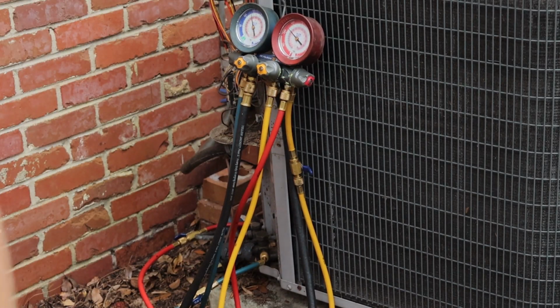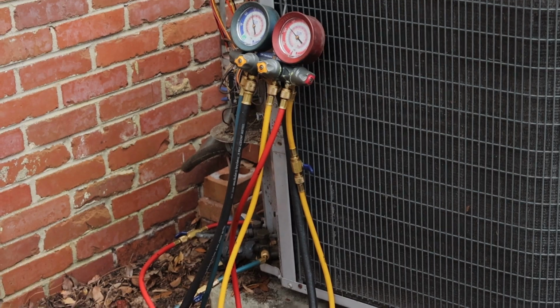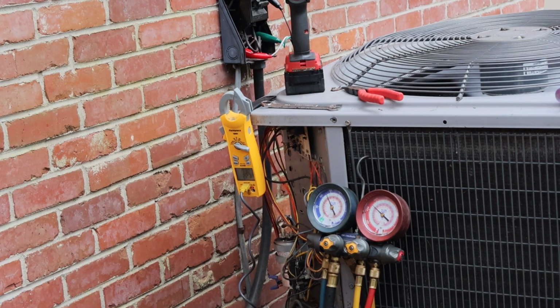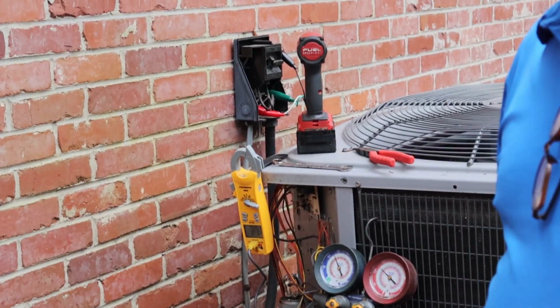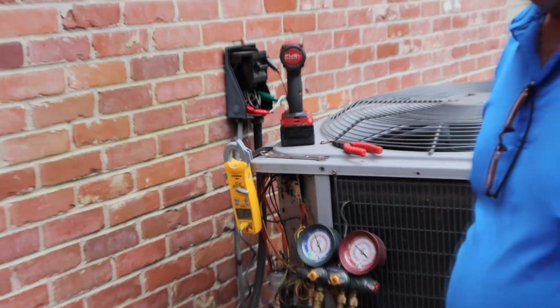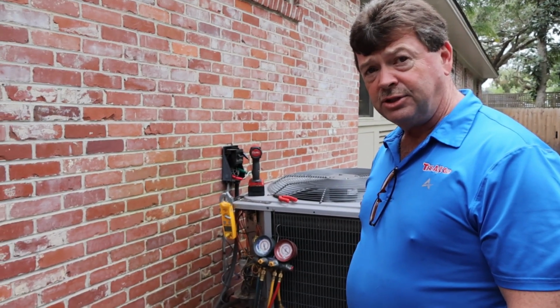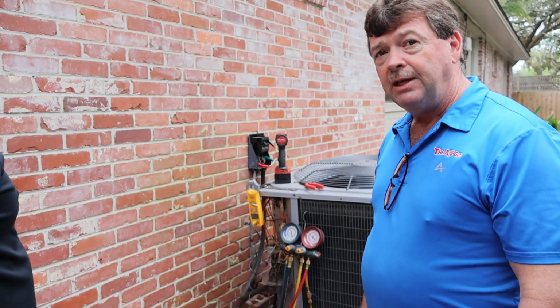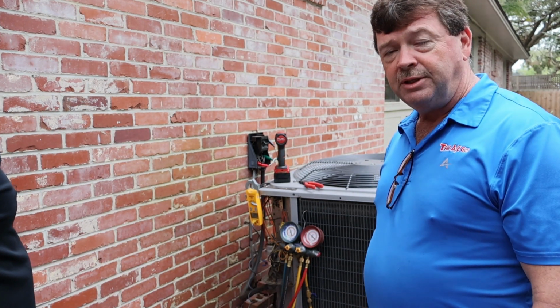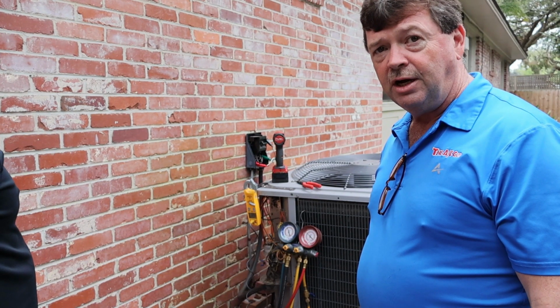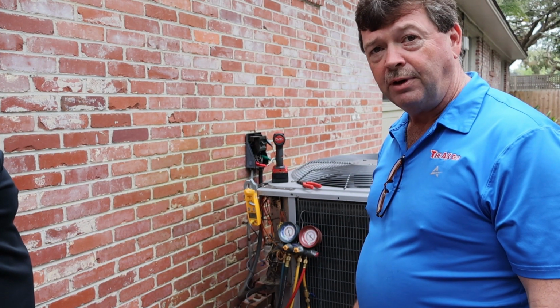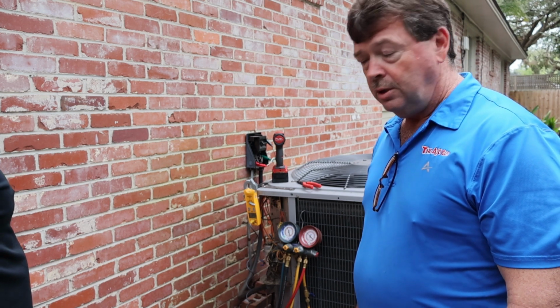Got dye in the system. That sucks. So he's going to confirm that the Freon charge is what the manufacturer determines it should be at these conditions. Once he does that, he'll also check the superheat, which is another measurement that you take to determine that the Freon pressure is moving properly through the evaporator coil.